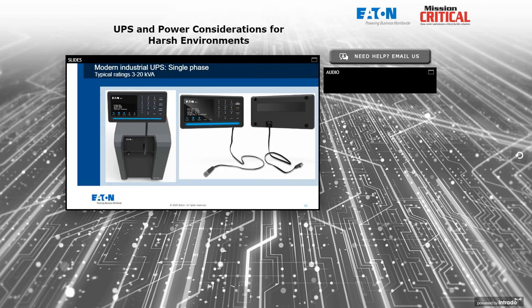So let's take a look at some modern industrial UPSs using our own product lines as example here, but there's many competitors in this industry that make very rugged, very capable UPSs. But in the small range, single phase, typically 3 to 20 kVA, one of the things that we see commonly, and we like to see, is a ferro-resonant technology. Ferro-resonant technology is not new, but it's common in this application because it is so rugged. It has the unique ability to do things like ride through brief outages and blinks without requiring special controls or without requiring a battery, at least for the very shortest types of interruptions.